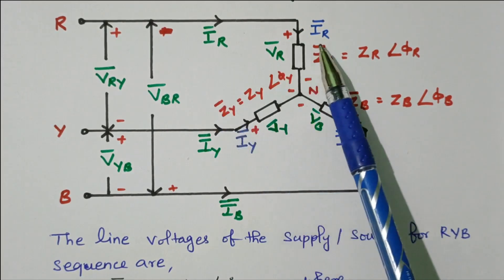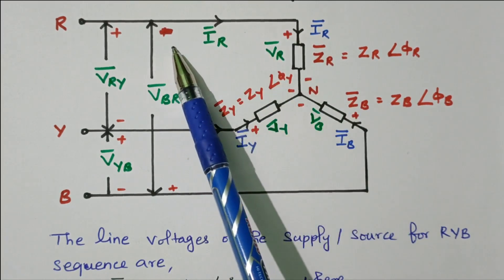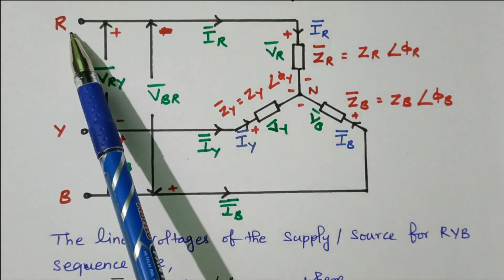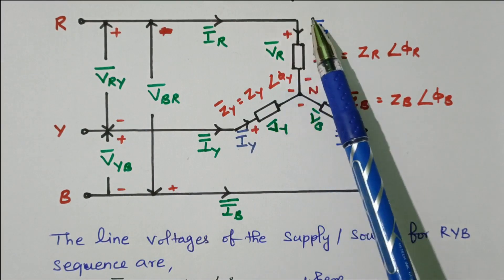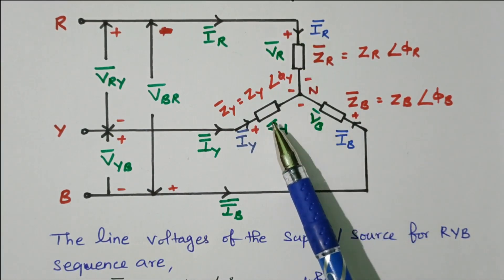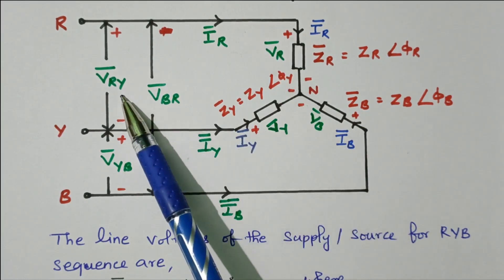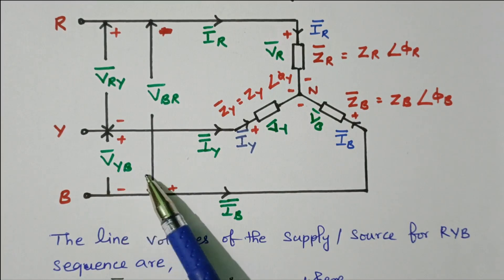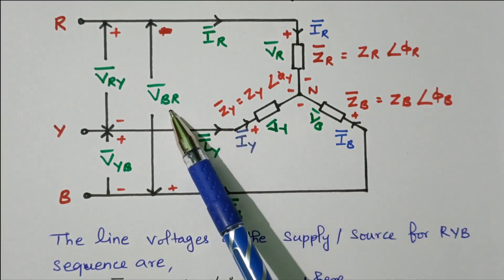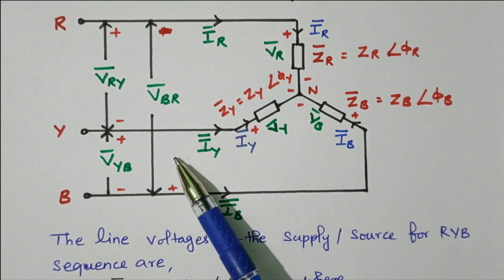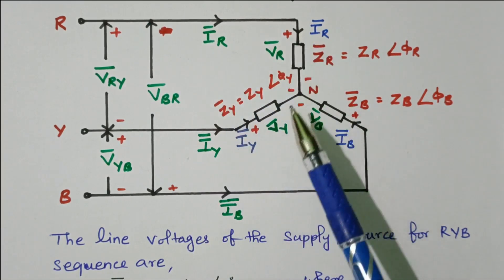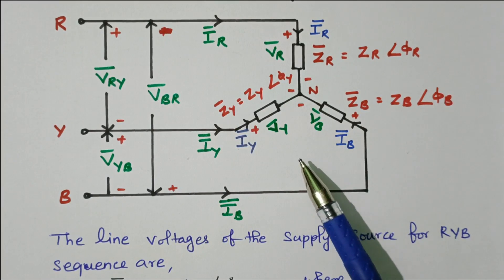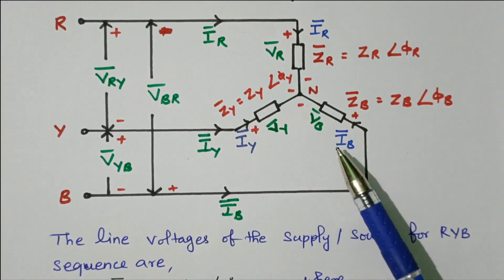The important thing is that line current and phase current are both equal in star connected systems. The current flowing from R-phase — line current IR — equals the phase current. But the voltage is different. Between R and Y we have VRY, but at the phase end two phases are available: R-phase and Y-phase. So VRY is the vector difference of R-phase and Y-phase. Similarly, VYB is the vector difference between Y-phase and B-phase, and VBR between B-phase and R-phase. In star connected, line current equals phase current, but line voltage is the vector difference of two phase voltages.